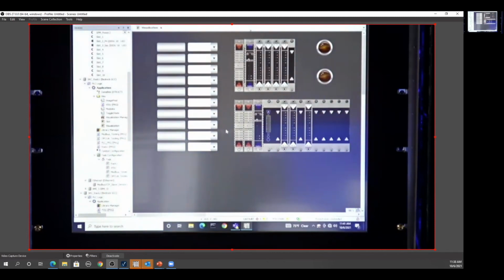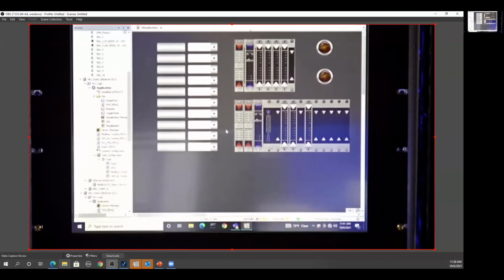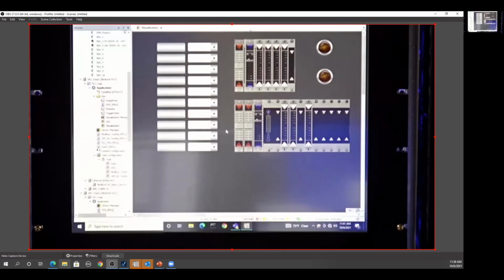This is a visualization screen we're developing for configuring your remote IO racks. In this case, a standalone controller talks to a remote rack, and you don't need to make downloads to the program to make changes. Through the visualization you pre-configure, you can set whatever modules are in whatever slot, since all this data is exposed over IEC code. You can build that into visualizations that can be web server based, but also local to the IDE itself, so you don't necessarily need to expose this to a web server. You can control all this in the IDE while building your visualizations, which really simplifies the process.